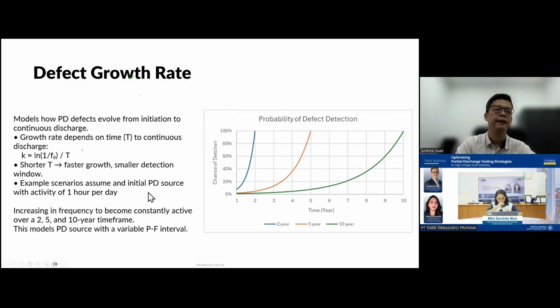The example scenario assumes an initiated PD source with activity from 1 hour per day, increasing in frequency to become constantly active over a 2 to 5 year time frame. This model covers PD sources with a variable point-to-failure interval, so detection rates can differ — sometimes it fails in 2 years, sometimes in 5 years. By 10 years, you can actually achieve 100% detection.